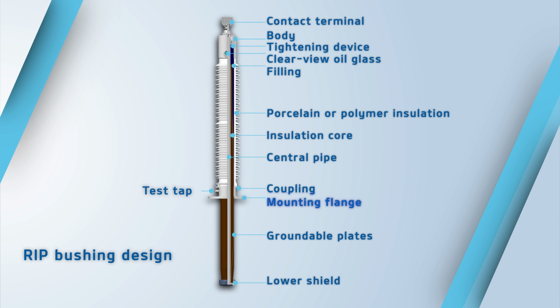The flange has eyebolts and a plugged air release hole for air outlet from the transformer. The hole can later be used for bleeding hose connection. Topside porcelain external housing with transformer oil or dry filling. In case of oil filling option, a body with clear view oil glass is used. There can also be used a polymer external insulation. Tightening spring unit at the top side of the bushings. Bottom corona shield, intended for equalizing the electric field in lower part of the bushing. Contact terminal for the bushing connection to a transformer lead.